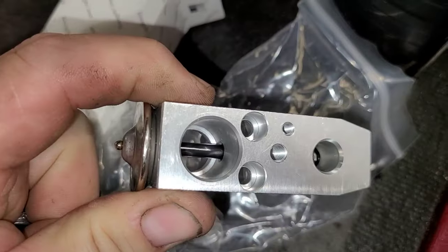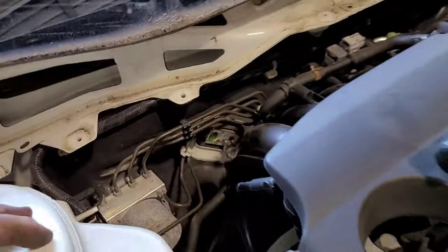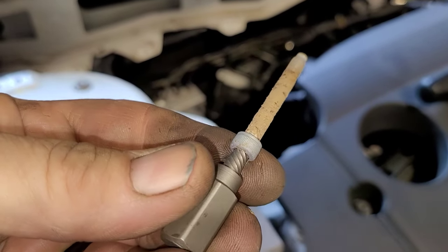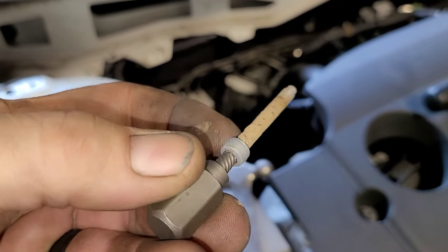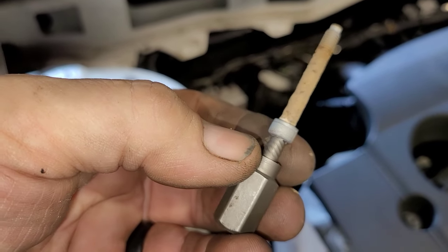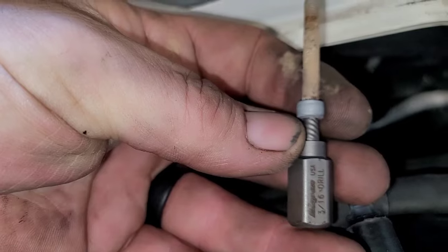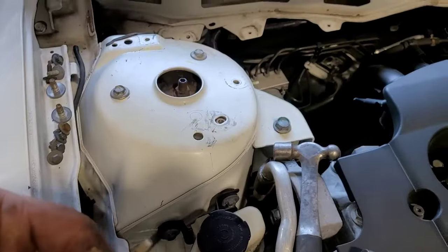Let me show you the new one, just so you know what it actually looks like. That's all it is - nothing super special. Now let me get the old one out. Both bolts are out, and one of them was a disaster - one of them wouldn't break free. You can see how corroded it is going through the tube. I wound up rounding out the head of the bolt with the socket, so I was able to get an easy-out in there - and that wasn't easy either. I wound up having to use a pry bar off of this bracket to hold tension on the assembly while I turned it with a ratchet, and I eventually got it to catch. It took quite a bit of effort - I actually thought at one point I was going to break the evaporator in there.